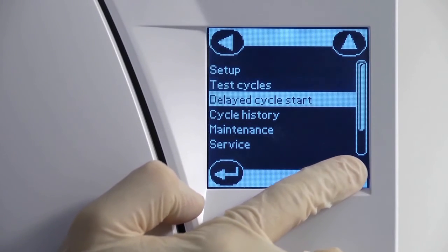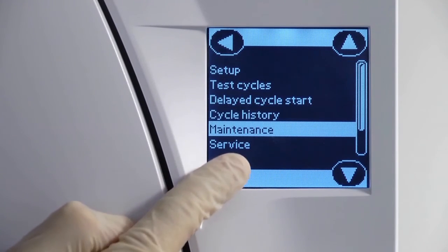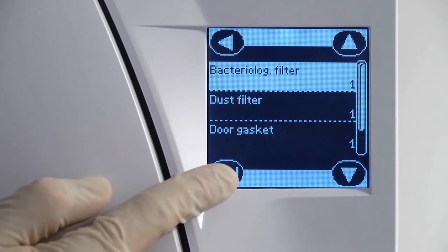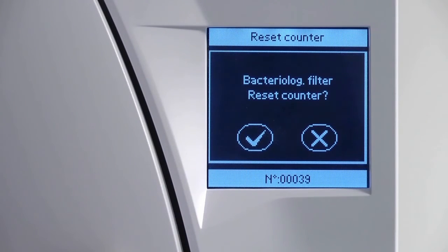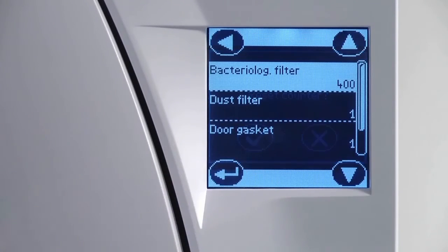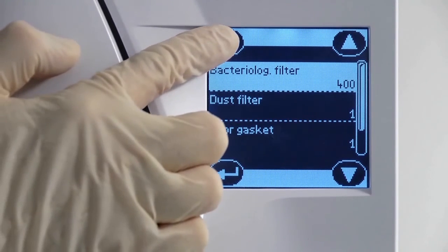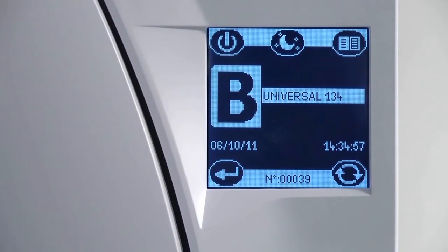From here, you can perform a manual reset of the bacteriological filter counter. Resetting the counter will ensure that the maintenance reminder automatically reappears after another 400 cycles have been completed. Now navigate back to the cycle selection screen to return your Lisa sterilizer ready for normal operation.